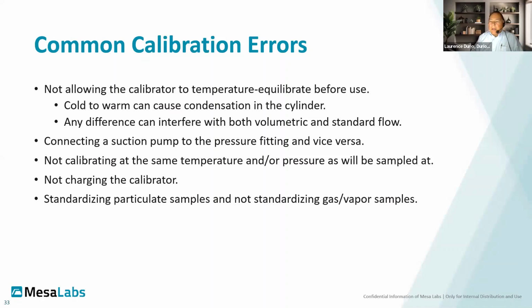Even if you have not gotten into condensation, you've got different temperatures. You're pulling, say, warm air into a cold calibrator. That air mass shrinks somewhat from the cold calibrator. The opposite happens going from warm to cold and cold to warm, and you get different volumetric and standardized readings than is reality. Connecting the pump to the pressure fitting instead of the suction fitting just simply doesn't work. You've got to have a good charge on the battery because that valve at the bottom requires quite a bit of current to operate it. And again, standardizing or not standardizing when you're supposed to do the opposite.